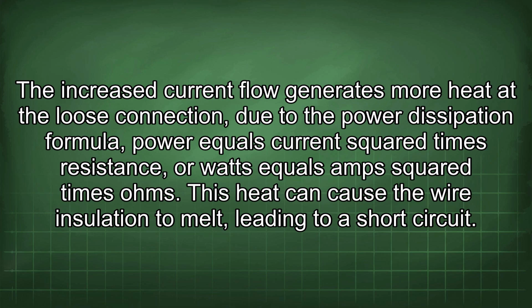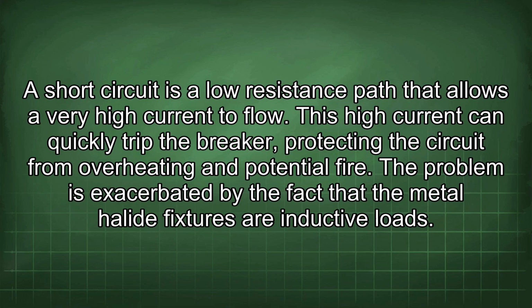The increased current flow generates more heat at the loose connection, due to the power dissipation formula: power equals current squared times resistance, or watts equals amps squared times ohms. This heat can cause the wire insulation to melt, leading to a short circuit. A short circuit is a low resistance path that allows a very high current to flow. This high current can quickly trip the breaker, protecting the circuit from overheating and potential fire.